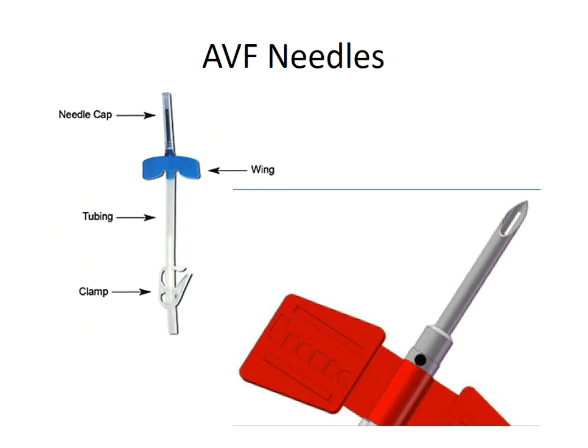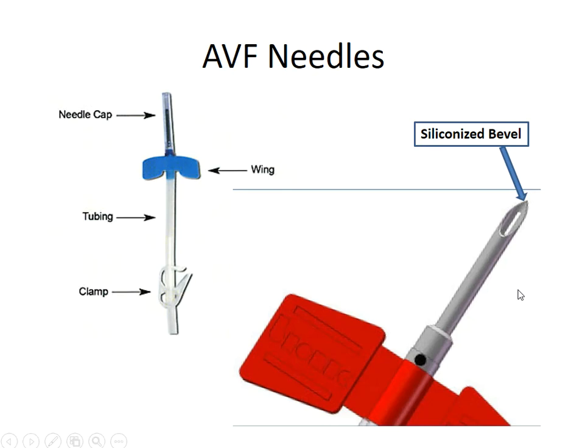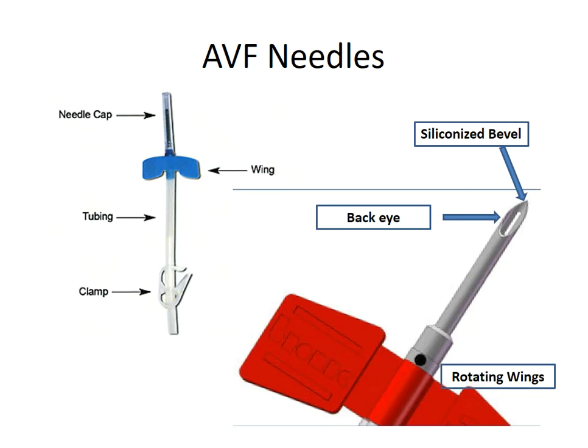The blood circuit starts from the arteriovenous fistula needles. The AV fistula needle has a needle, wings, tube, and a clamp. The needle has a siliconized bevel and a back eye, with rotating wings. These rotating wings can help in repositioning of the needle during dialysis.